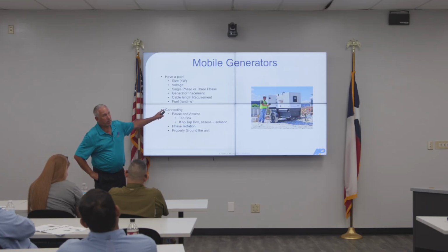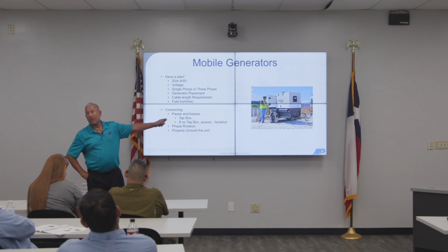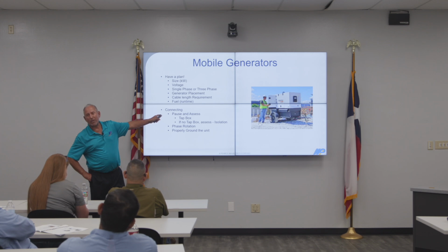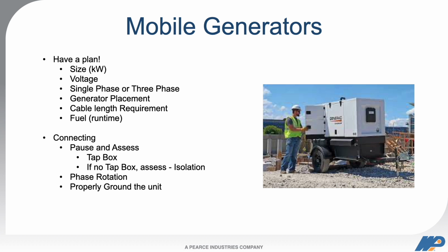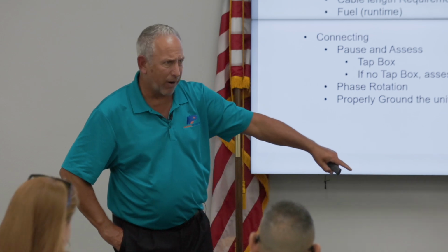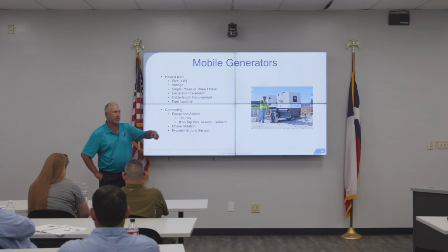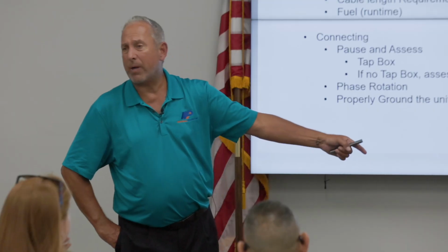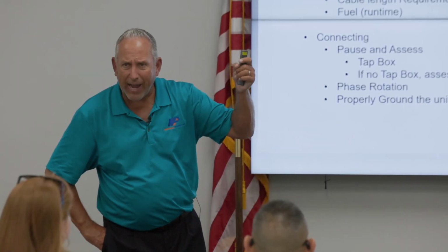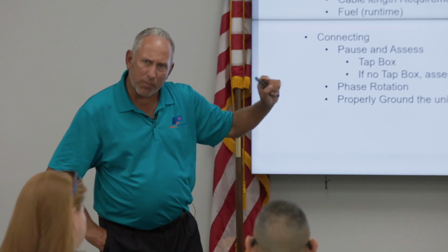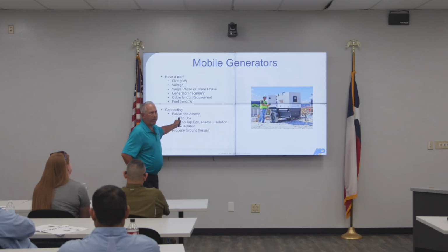The code people know this. What generally starts happening is you're dropping cables out of things in the field. Normally the generator would be hooked up there, but now you have to get cables, drop them, and bring other cables in to where the old generator was. Or if there was no generator and you're doing your building, you're doing the same thing but with utility cables. That becomes a problem. People strip a lug out, and that becomes a problem too. So they're hammering down on this.